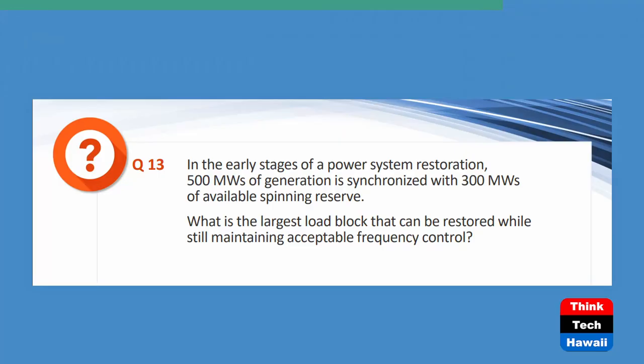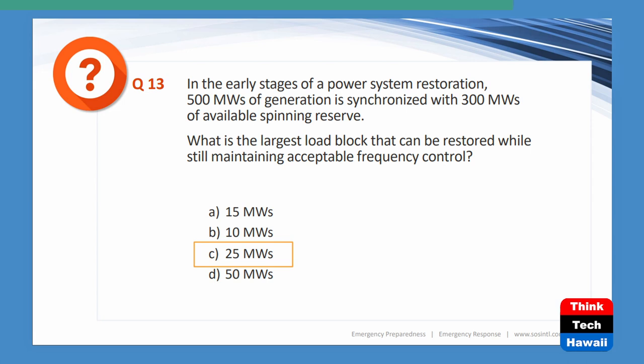All right, the next question. In the early stages of a power system restoration, 500 megawatts of generation is synchronized with 300 megawatts of available spinning reserve. That means that you've already picked up 200 megawatts of load. What is the largest load block that can be restored while still maintaining acceptable frequency control? Usually the rule of thumb is 5% of the synchronized generation, right? And so 5% of 500 is 25. And that's really what you were using. So the answer here is either A, 15, B, 10, C, 25, or D, 50. So here the answer will be 25.